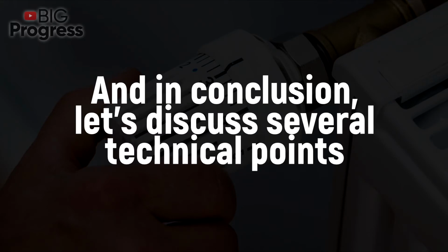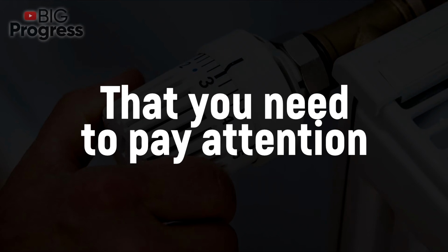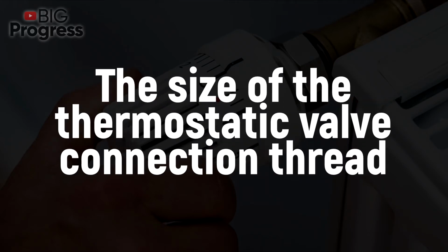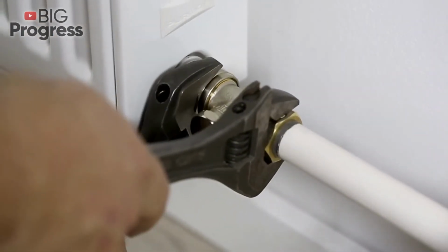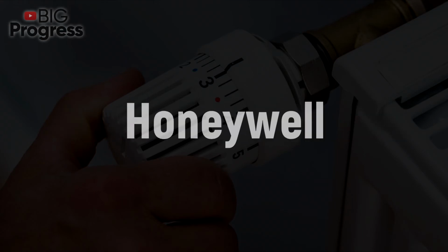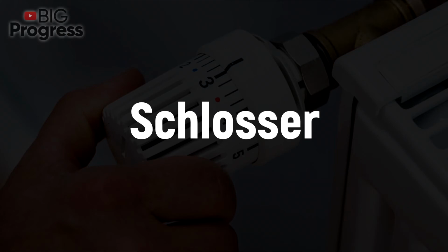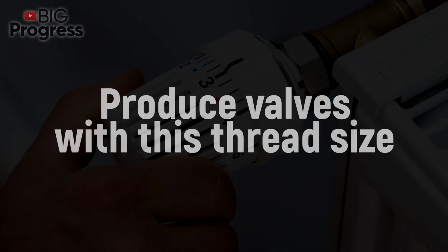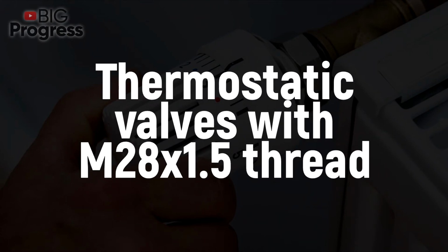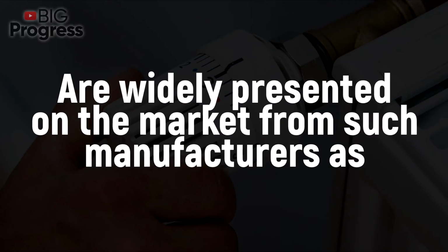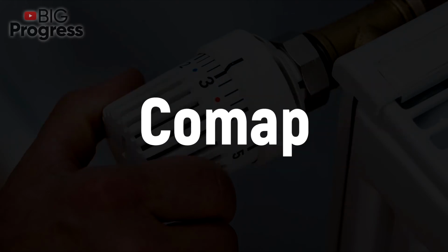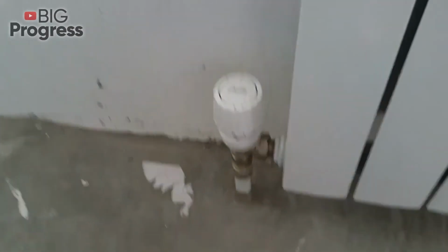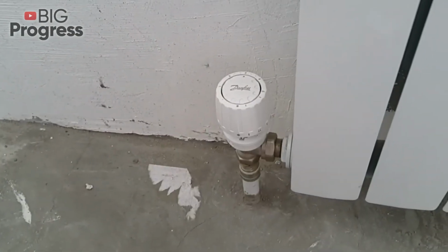And in conclusion, let's discuss several technical points that you need to pay attention to before choosing a thermal head. The size of the thermostatic valve connection thread. A universal size for mounting a thermal head is the M30 by 1.5 connection thread. Manufacturers like Oventrop, Honeywell, Valtech, M&G, Heimeier, and Schlosser produce valves with this thread size. Thermostatic valves with M28 by 1.5 thread are widely presented on the market from such manufacturers as Hertz, Comap, Patinaroli, and Giacomini. Danfoss has its own patented click system with M23.5 by 1.5 connection thread.